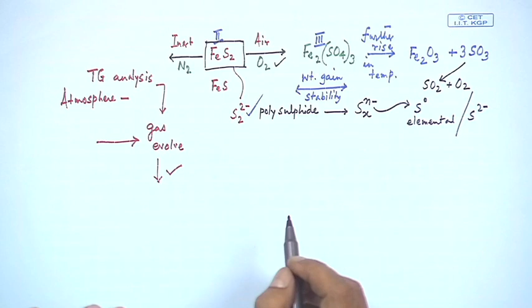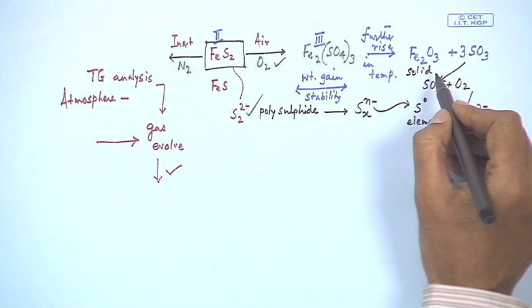So, this is a very delicate process at this point, because the delicate step is the sulfur trioxide formation at a very high temperature, and the atmosphere is also air and oxygen. So, we expect that sulfur trioxide, the most stable oxide form of the sulfur, will be there, but it so happens that the sulfur trioxide will break again into sulfur dioxide and oxygen back, which we have been utilizing from air or from the dioxygen environment. So, this will leave the crucible and go out from the sample chamber, and out from the instrument. The only thing that remains as a solid on the crucible is ferric oxide, which will carry the weight for ferric oxide only.